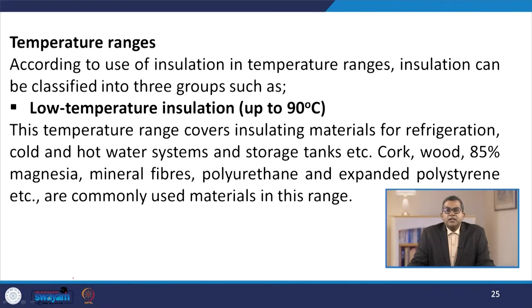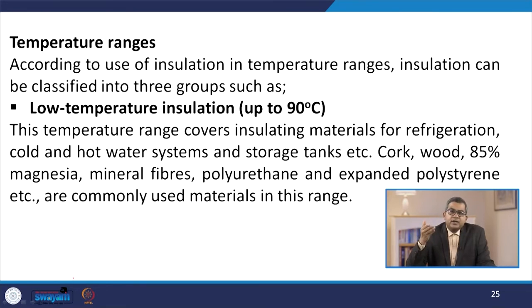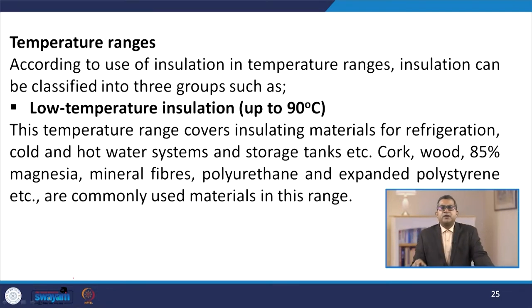Let us talk about temperature ranges. According to use, insulation can be classified into three different groups. Low temperature insulation is up to 90°C, covering insulating materials for refrigeration, cold and hot water systems, and storage tanks. Commonly used materials in this range include cork, wood, 85% magnesia, mineral fibres, polyurethane, and expanded polystyrene.